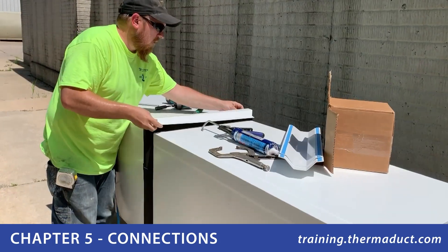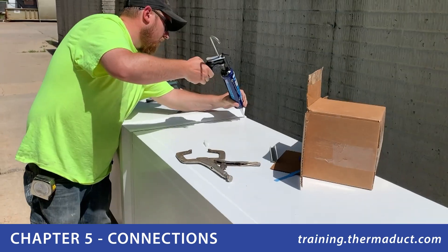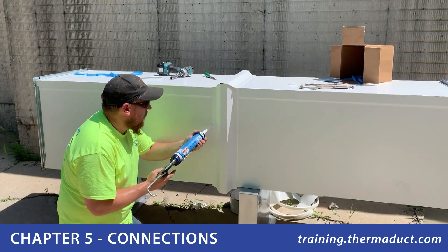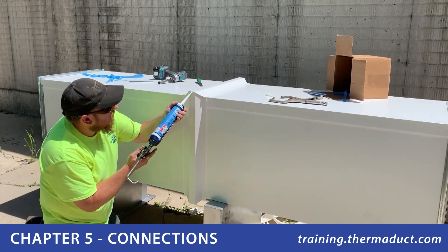And finally, a weather-resistant covering is installed and sealed. Certain areas on the bottom side of the mitered cover should not be sealed to ensure any minor air leakage present at the connection will not eventually pressurize the cover.